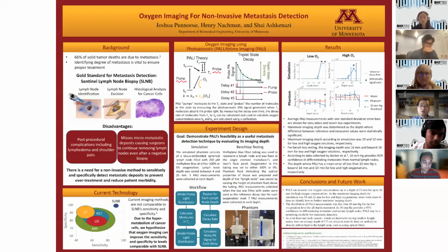So we have the same resolution as an ultrasound transducer. Depending on the bandwidth of your transducer, that affects the resolution. But typical ultrasound transducers can detect from around 200 microns. Around 200 microns is the resolution.